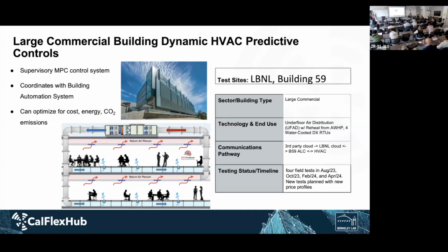For heating, in the perimeter zones of the building, there are fan coils served by a heat pump, and there the MPC can change the set point in each of the zones to trigger a heating request so that the heat pump will turn on and the room will be warmed up. So the MPC integrates with the existing control logic much more deeply than it would in a smaller commercial building, which requires a more custom interface.